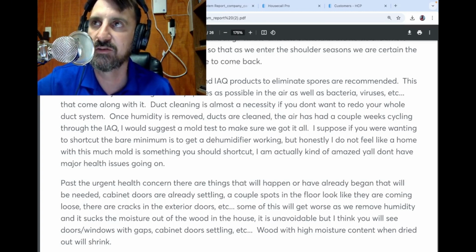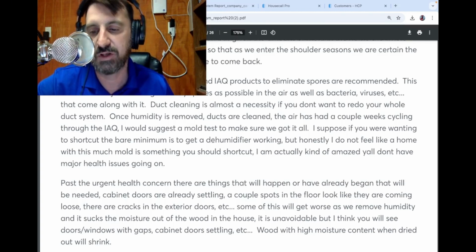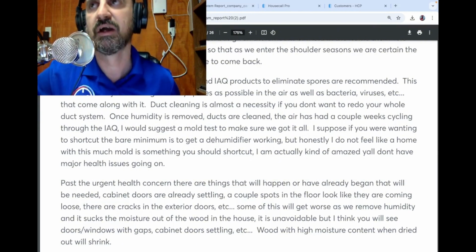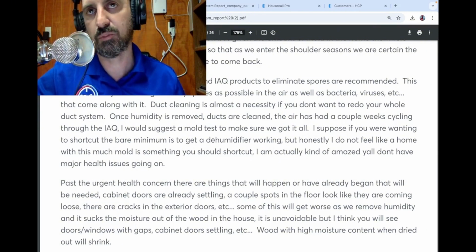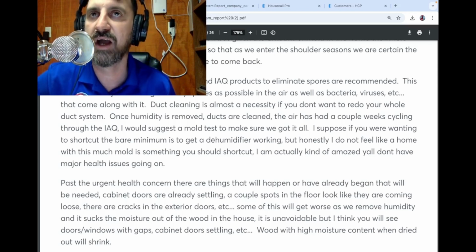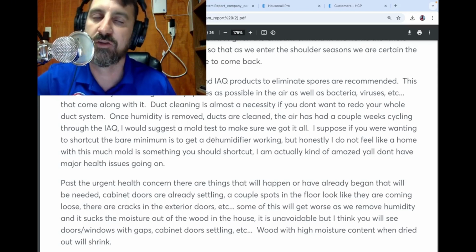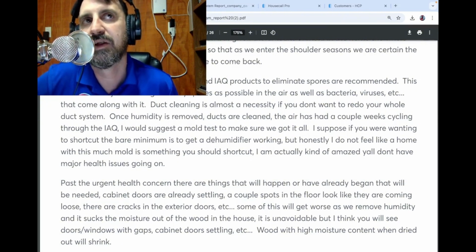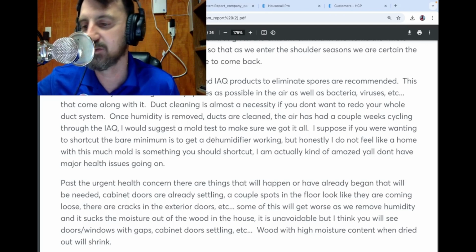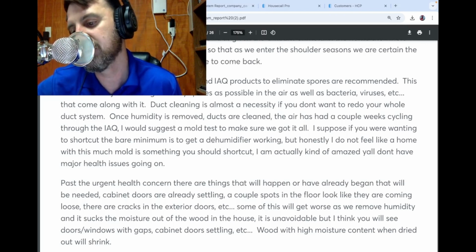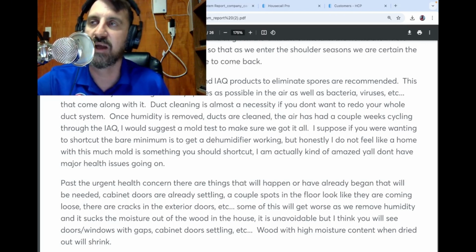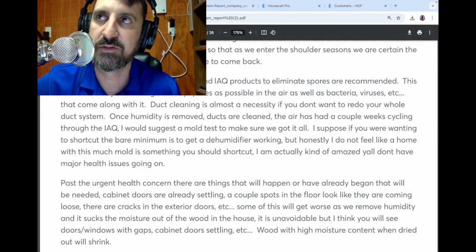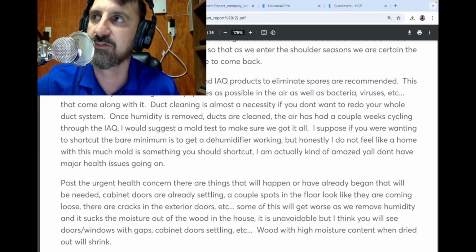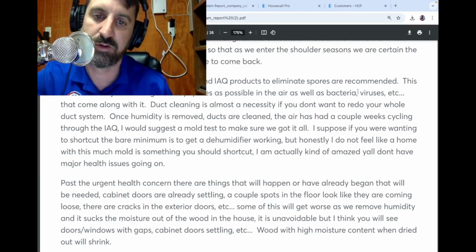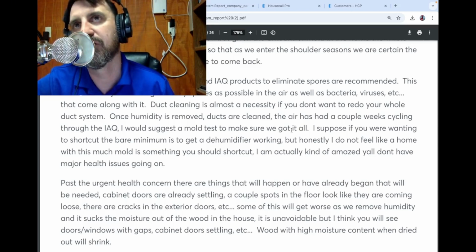But from there you can hook up UV lights, you can hook up an ionizer, you can hook up an air scrubber, and they'll all power off the central control, but you're really addressing all of the issues. The ionizer charges particles so that they combine together and make bigger particles so that your filter is more effective. The number that the government testing gave them is that it makes it at least 20% more effective. They said they really feel like the number is closer to 50, but the number that whatever FDA or whatever told them they have to use is 20. So, but that makes your filter more effective.